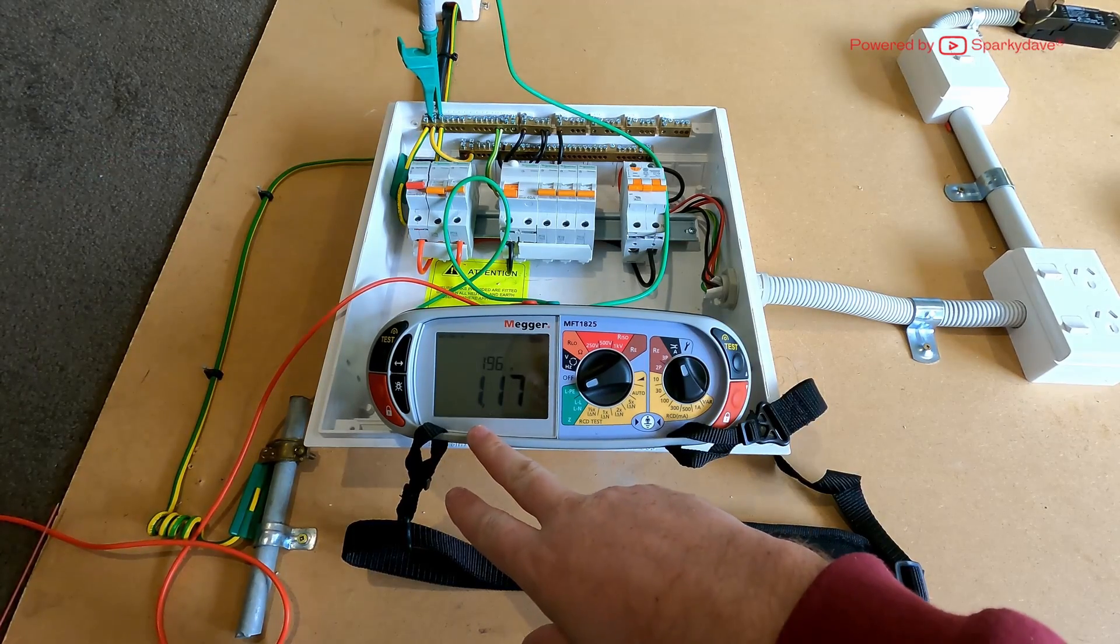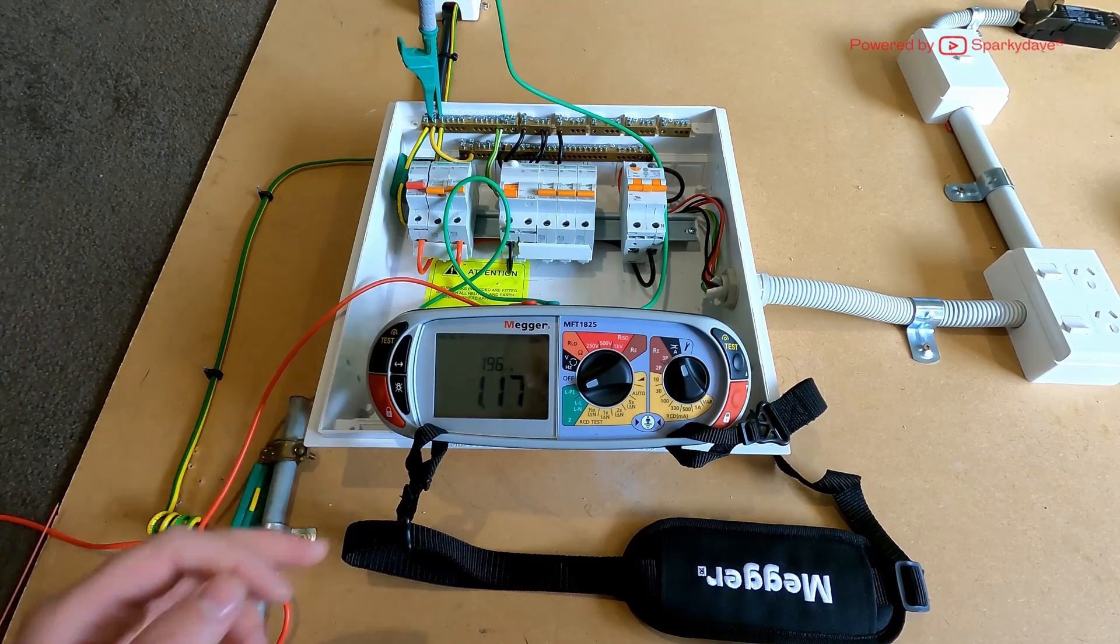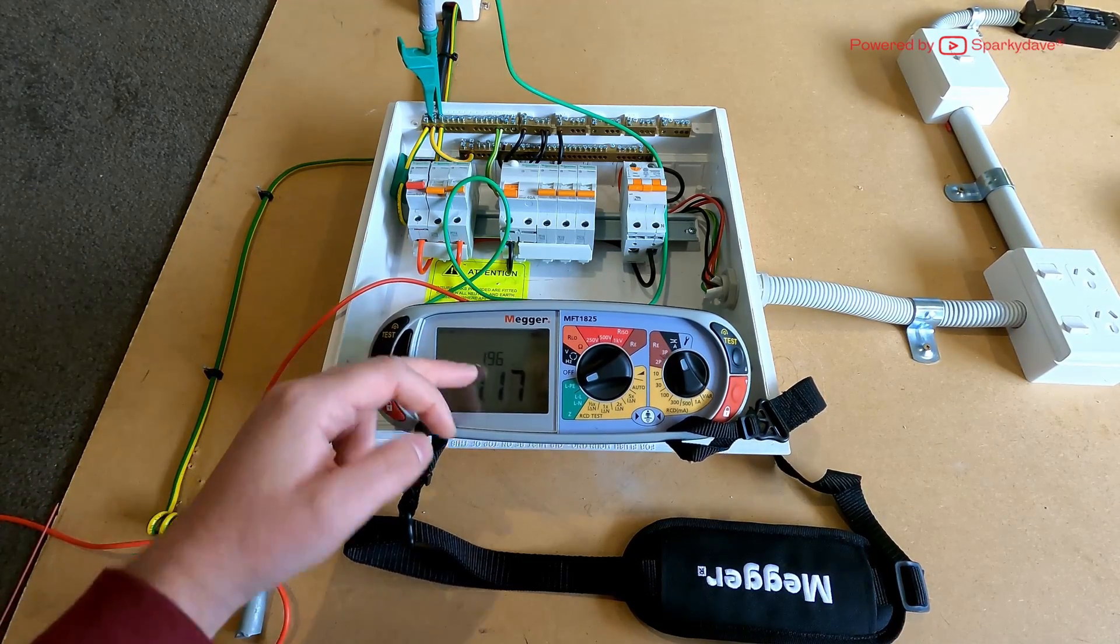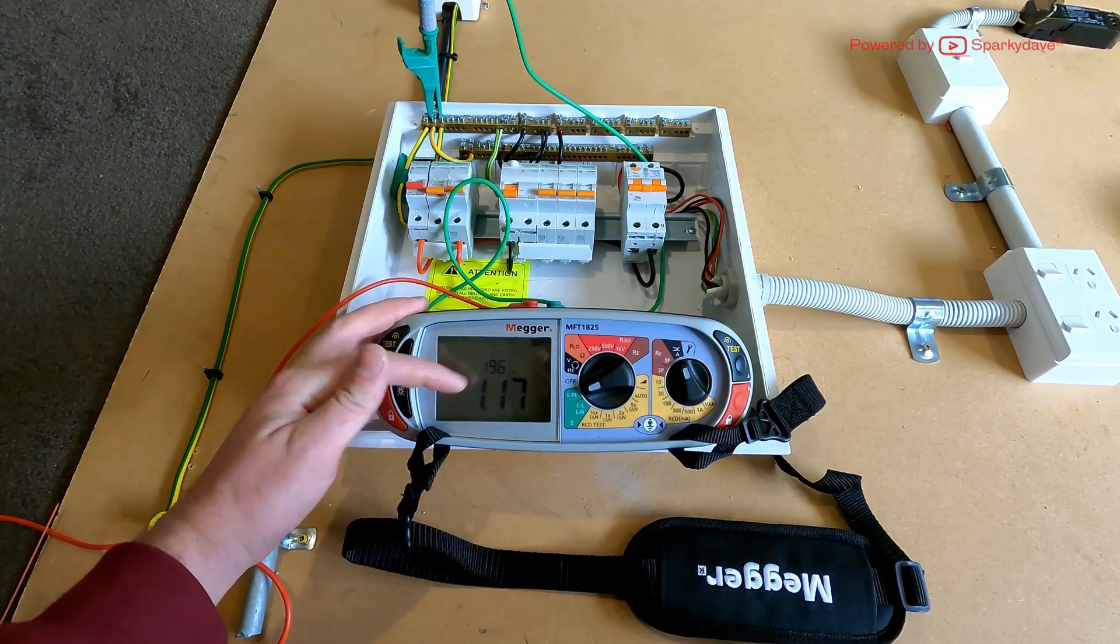This reading here that we've come up with is our impedance, and then the one above it is our prospective short circuit current. So that is just voltage over impedance, so 230 divided by 1.17 equals 196 amps.